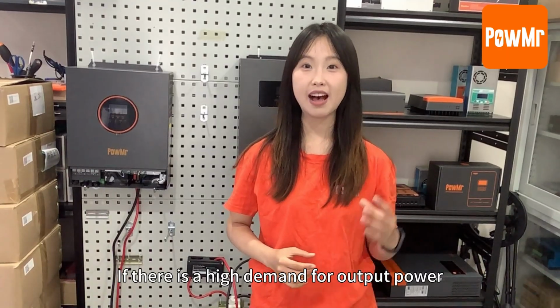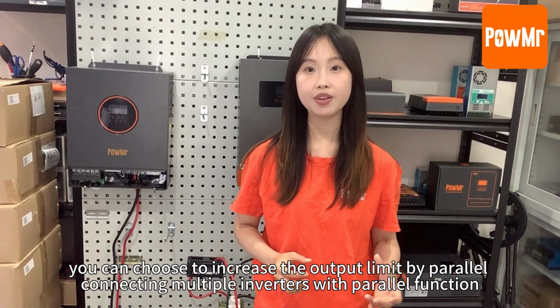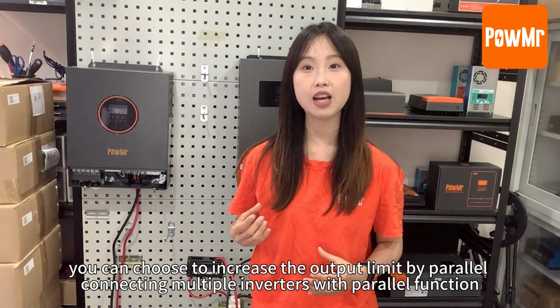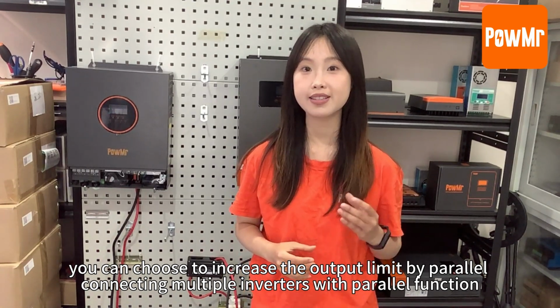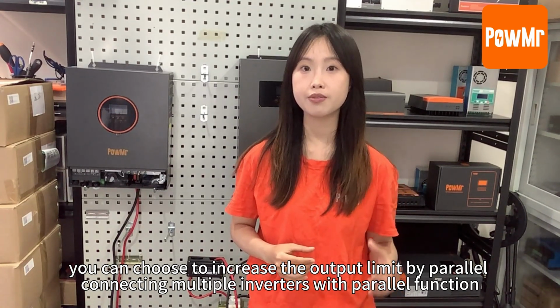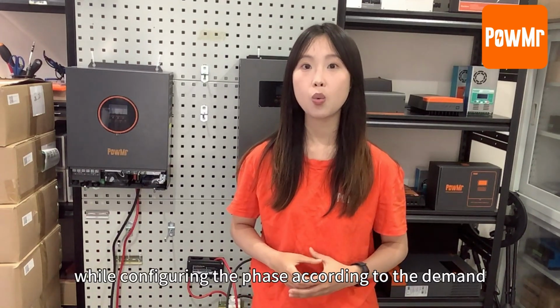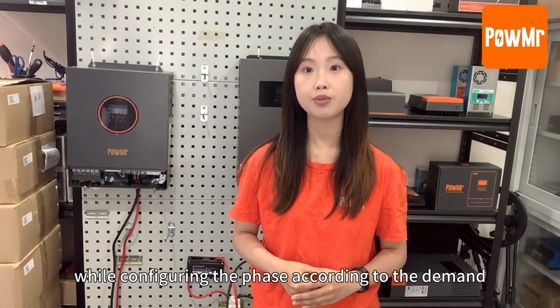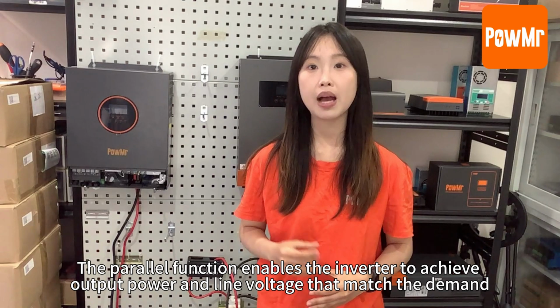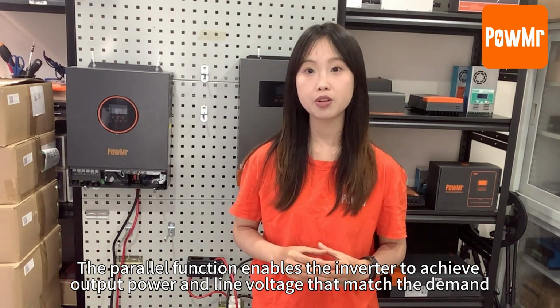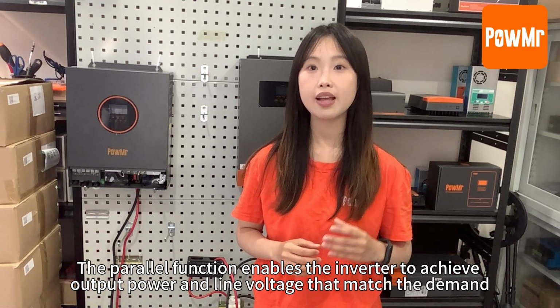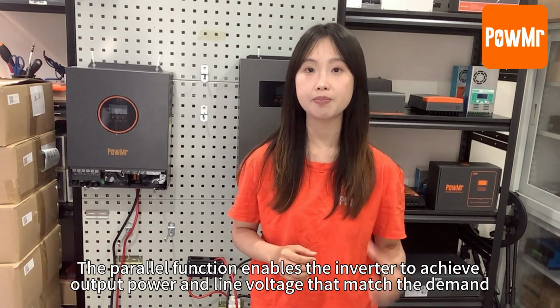If there is a high demand for output power, you can choose to increase the output limits by connecting multiple inverters with parallel function in parallel. Why configure the phase according to demands? The parallel function enables inverters to achieve output power and line voltage that match the demand.